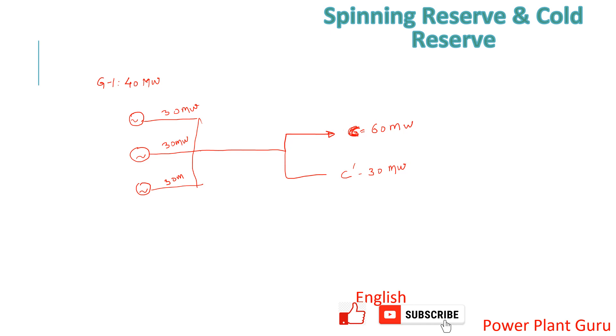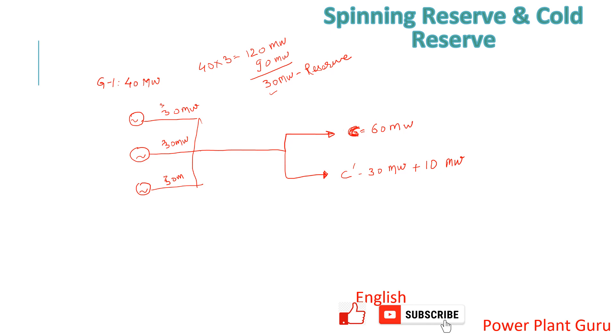Now let us calculate the spinning reserve. Total capacity is 40 into 3 which is 120 megawatt, and the demand is 90 megawatt. So 30 megawatt is the reserve capability available. Let us say there is a case of sudden demand rise — a 10 megawatt increase. If you have 30 megawatt of reserve there will be no problem in meeting this 10 megawatt increase. So at roughly 33.3 megawatt per generator you will be able to supply 100 megawatt. Here your reserve is coming into play.